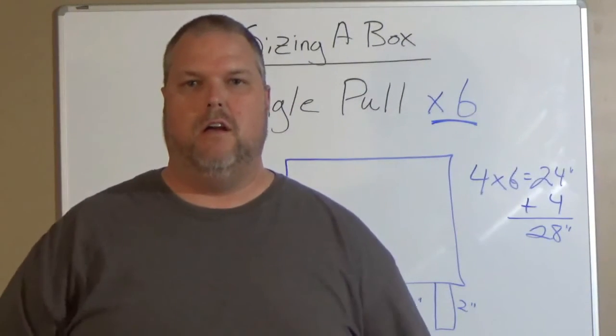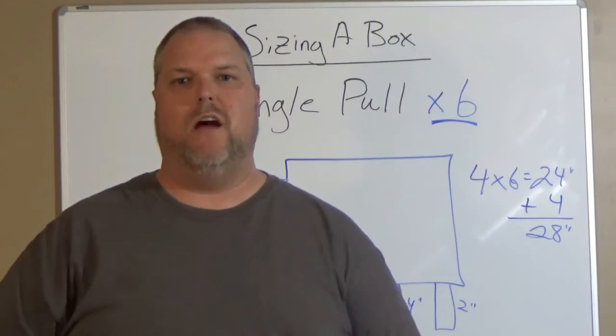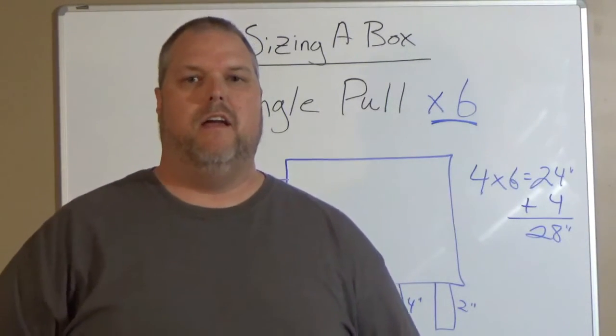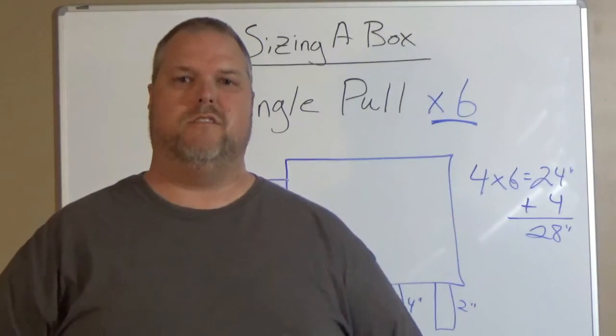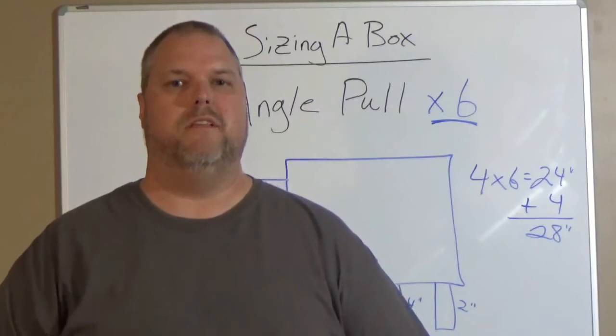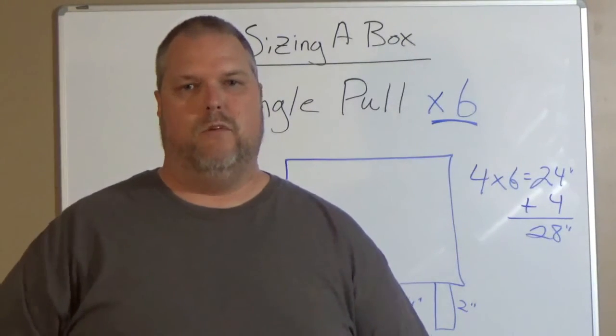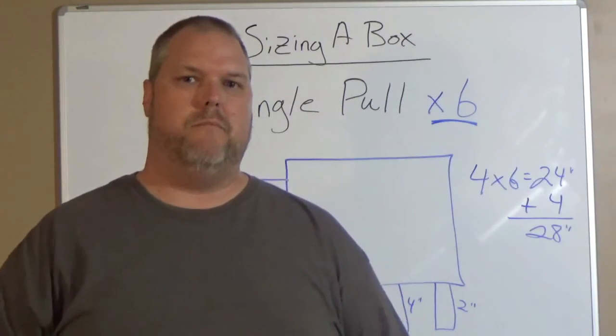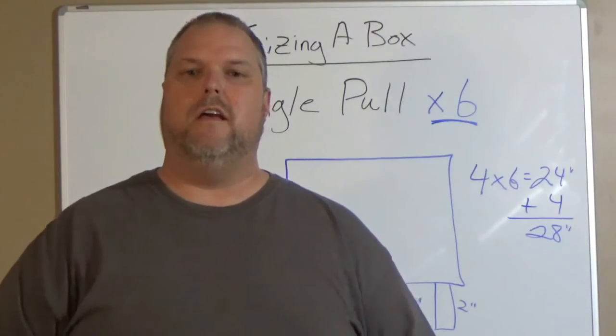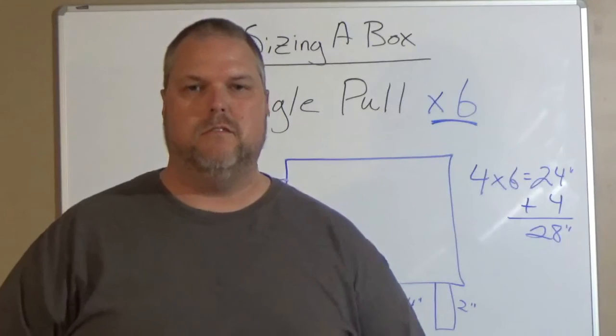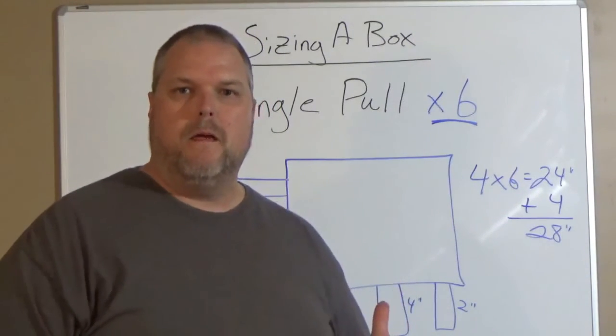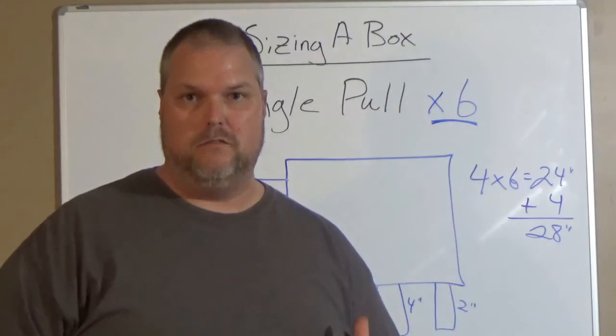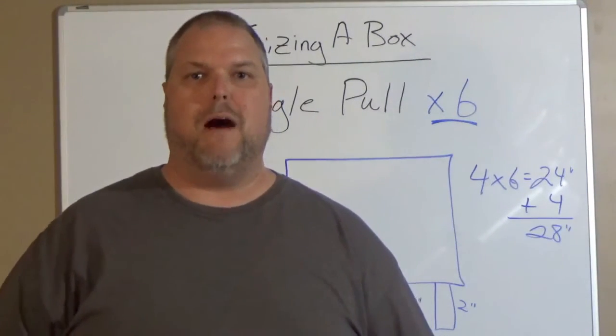Obviously, guys, we have the same conduit going in one way as we do have it coming out the other way. So if we did have more conduits, we have to size them a little bit different. So remember, every scenario is going to be a little bit different. You just have to remember that you take the largest conduit, multiply it by 6, add the additional conduits to that number, and that gives you the size of your box.